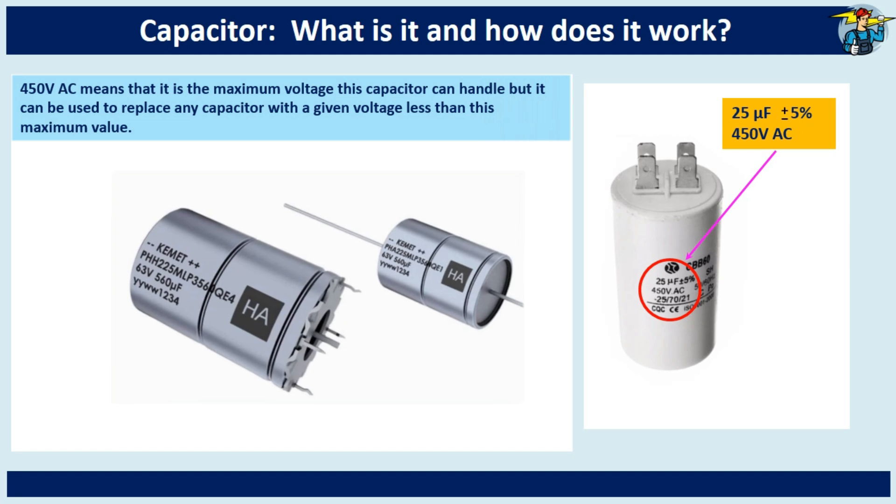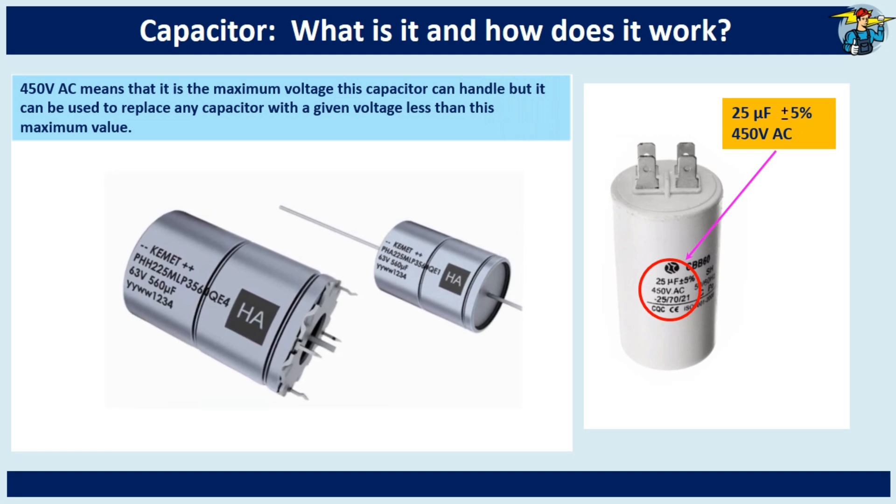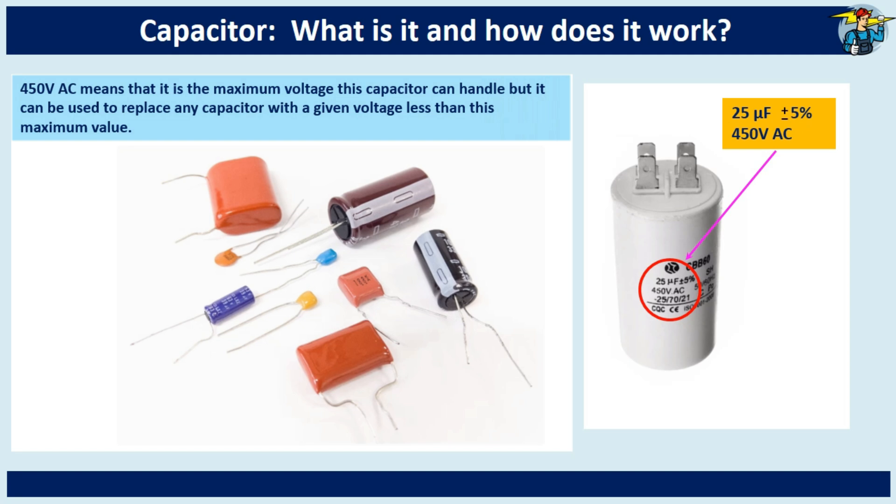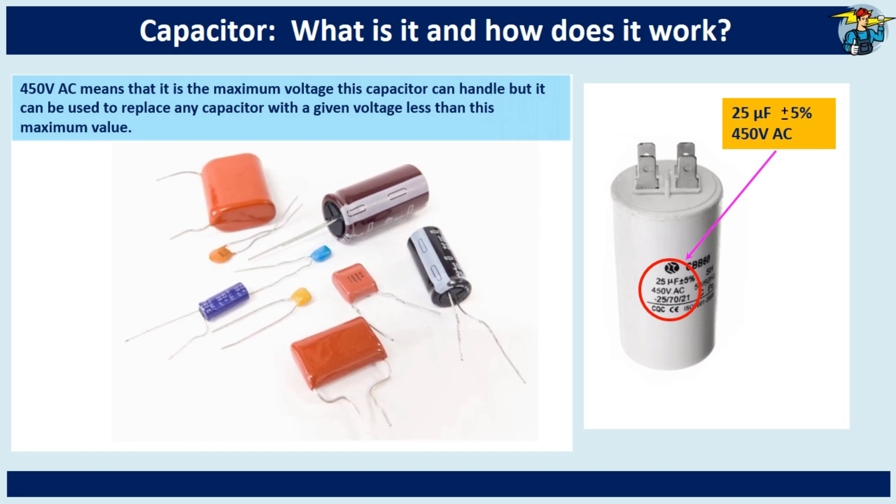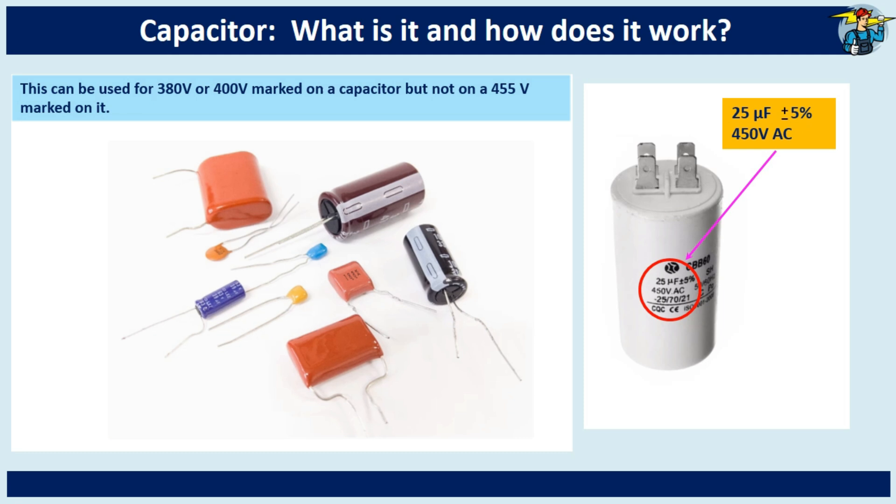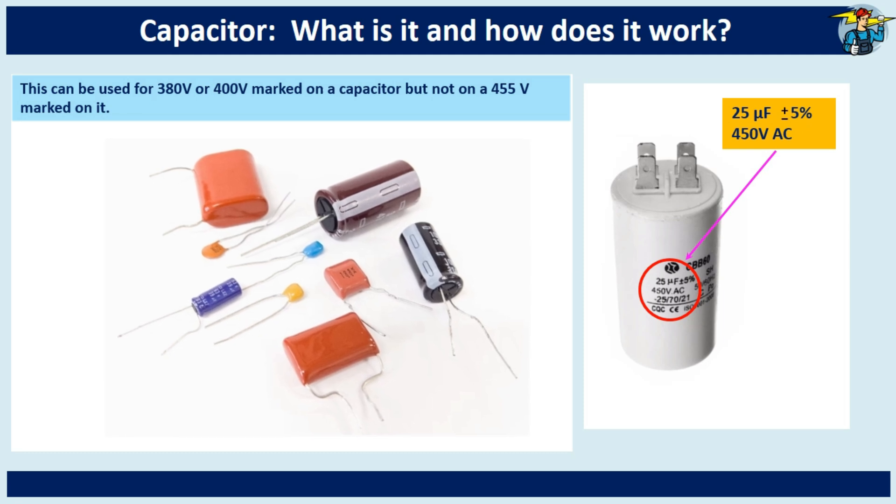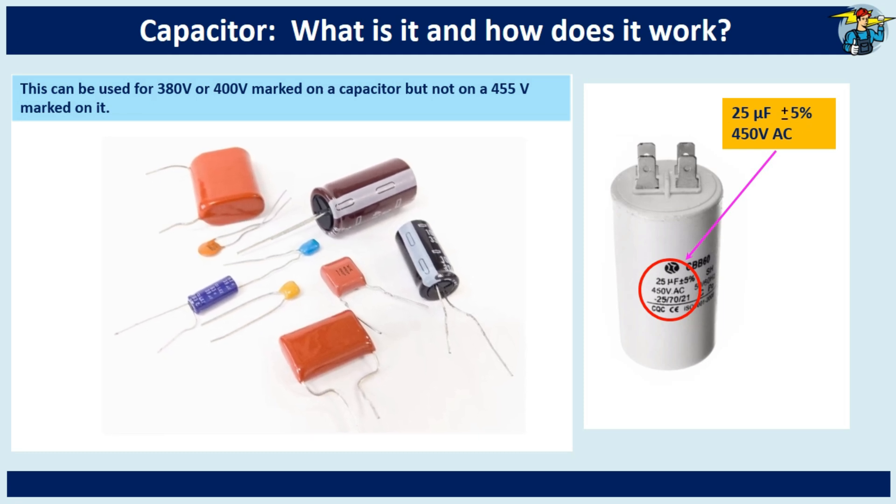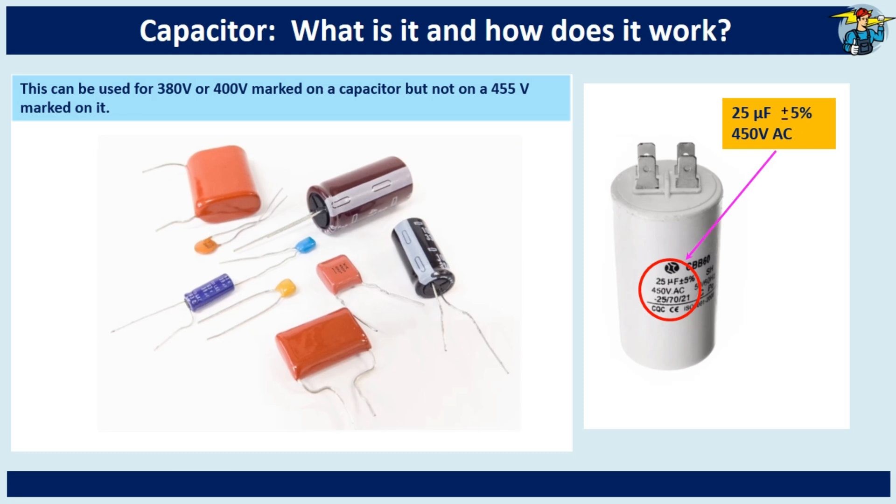450 volts AC means that it is the maximum voltage this capacitor can handle, but it can be used to replace any capacitor with a voltage less than this maximum value. That means it can be used to replace a 380 volts or 400 volts capacitor but not a 455 volts capacitor.